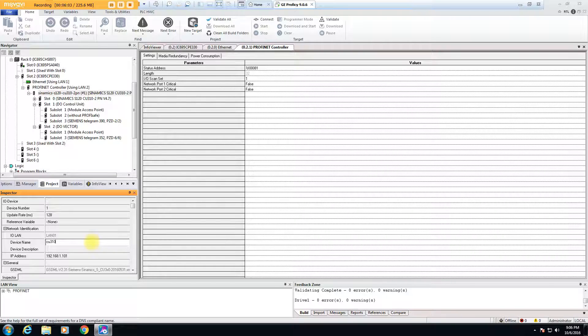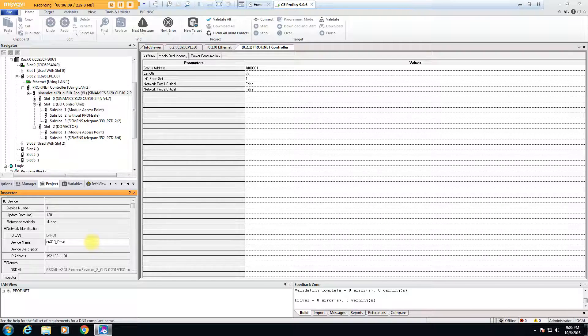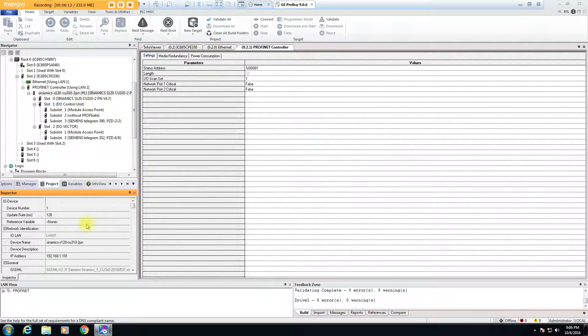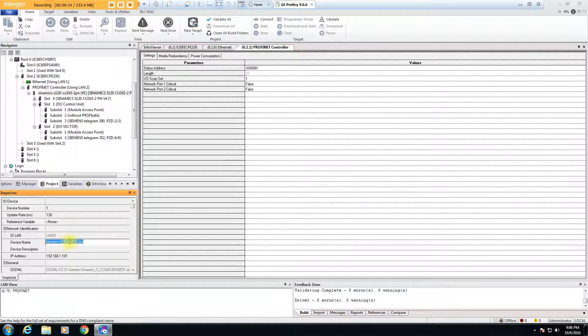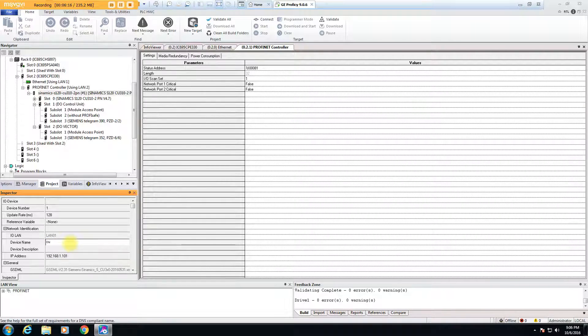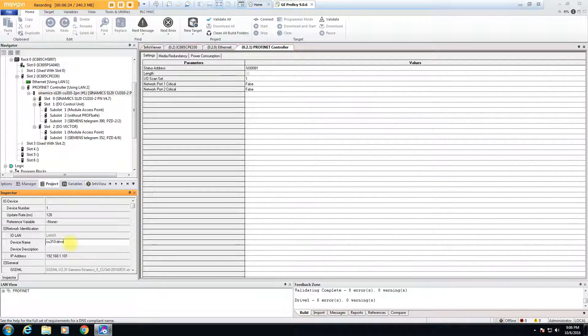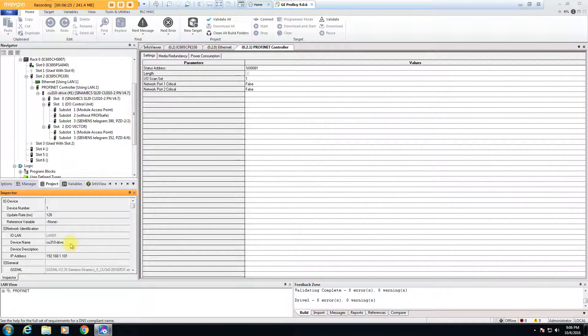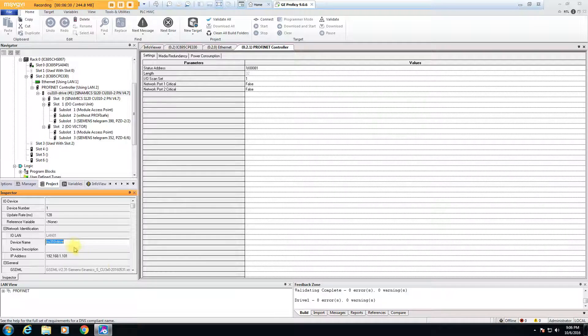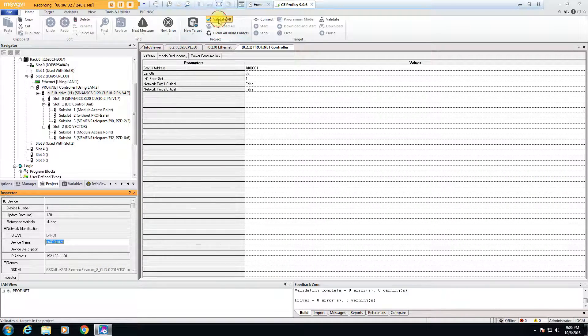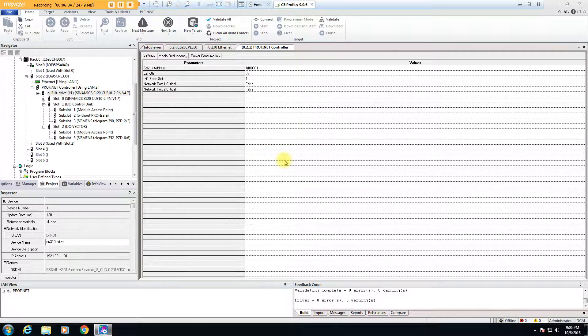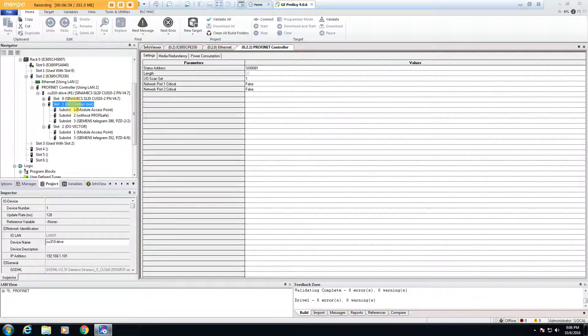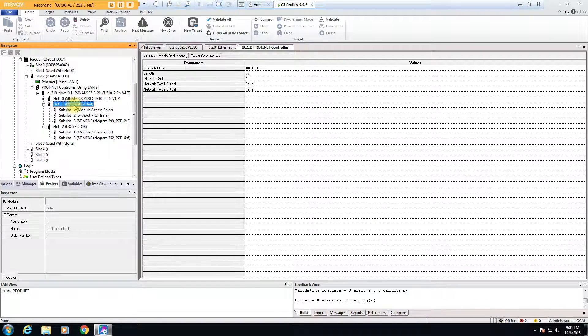I got to make sure that you've given the drive a PROFINET name, so that it has both the address and the name of the drive. They have to match, and it has to be a hundred percent. The name and the address has to be exactly what you set in the drive. You got to set the same thing in the drive itself because this is just in the PLC program, or they won't connect.